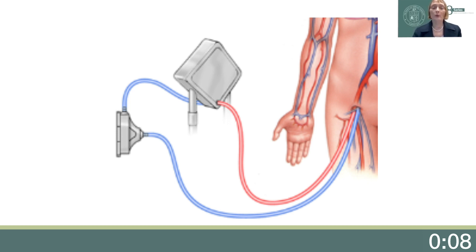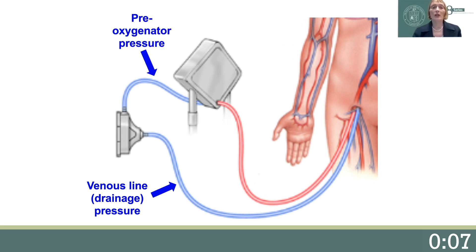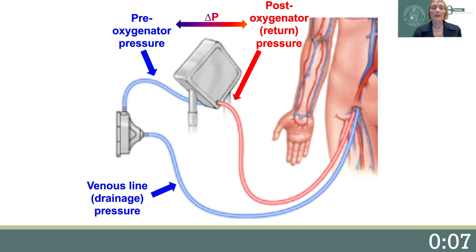The four key pressures to monitor in the ECMO circuit are: number one, the venous inflow or drainage pressure; number two, the pre-oxygenator pressure; number three, the post-oxygenator or return pressure; and the delta P or trans-oxygenator pressure. Failure to identify abnormalities in these four pressures and recognize interventions to resolve them can lead to sudden ECMO circuit failure and clinical catastrophes such as embolic stroke.